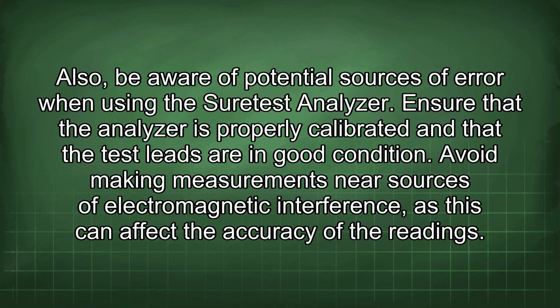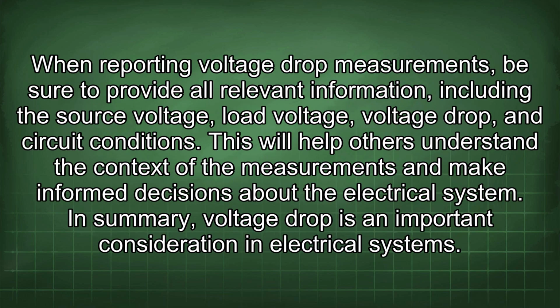Also, be aware of potential sources of error when using the Suretest Analyzer. Ensure that the analyzer is properly calibrated and that the test leads are in good condition. Avoid making measurements near sources of electromagnetic interference, as this can affect the accuracy of the readings. When reporting voltage drop measurements, be sure to provide all relevant information, including the source voltage, load voltage, voltage drop, and circuit conditions.